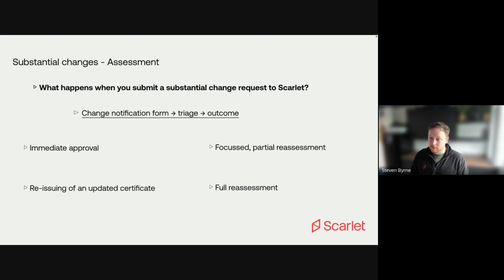The final one is a full reassessment. This is more common when you get up to class 3 medical devices. For class 2A and class 2B, we don't really see the full reassessment being a pathway that's taken by us, to be honest. So the summation of that is to give you an idea that just because you've got a substantial change doesn't mean that the workload put in by the notified body is always going to be very time consuming or laborious. So do have confidence that you can push a substantial change to us and expect you will get approval on it relatively quickly.